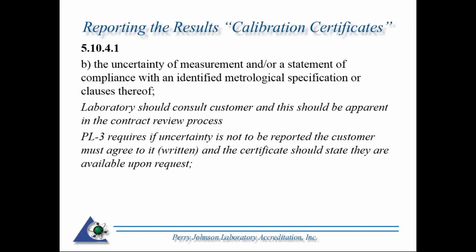PL3, which is PJLA's policy on measurement uncertainties, we require if uncertainty is not to be reported, the customer must agree to this in writing. So our assessors will be looking for objective evidence of this. And the certificate should state they are available upon request.